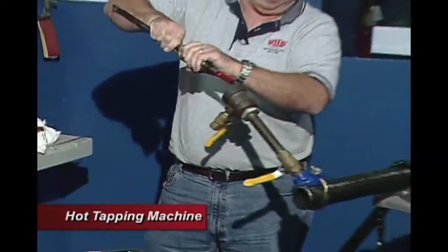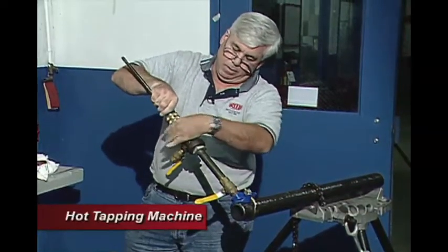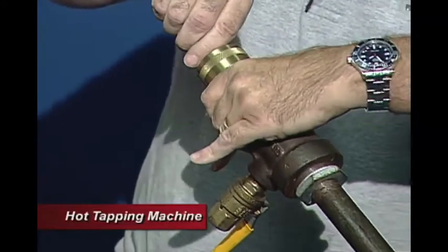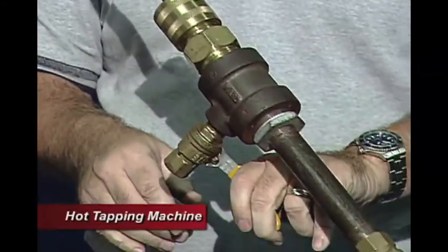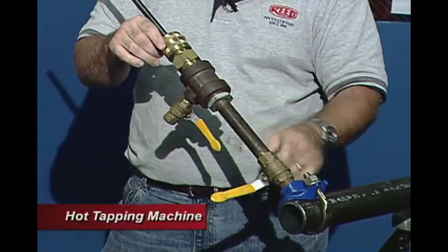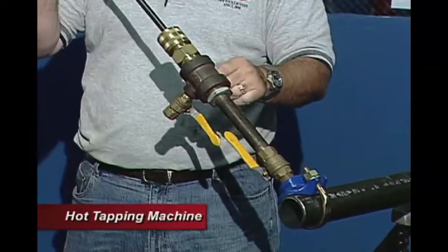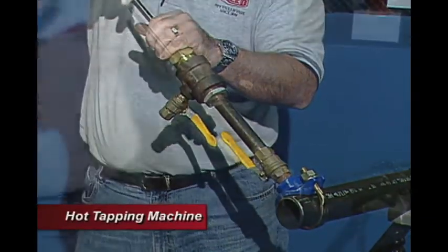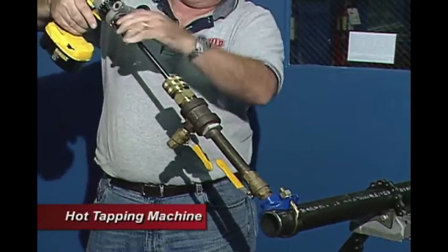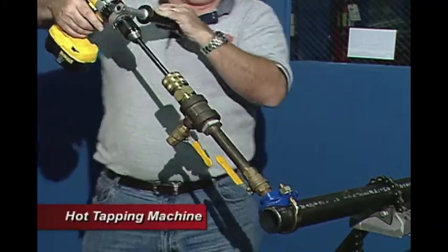Now we're going to reassemble this. We pull our boring bar all the way back and feed our threaded body into the T-valve. We want to make sure our bleeder valve is closed. Now this system is not pressurized — we need to pressurize this so we can get our hole saw down through the valve. So we open this up, which pressurizes the line, and feed our boring bar down to the pipe. We reattach our drill and drill the hole.